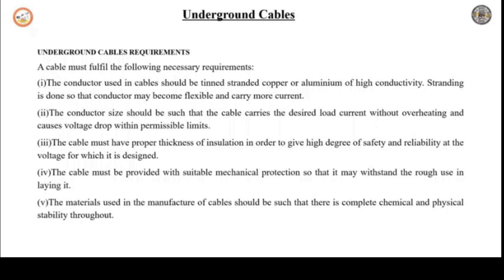What are the basic necessary requirements of the cables? The size of the conductor used must be such that it should carry the specified load without overheating and keeping the voltage drops well within the permissible limits. At the voltage level for which cables are designed, the insulation thickness must be proper so as to provide a high degree of safety and reliability. The cables must be surrounded by a number of layers of additional insulation so as to give proper mechanical strength and protection, so the cables can withstand rough use at the time of laying them.